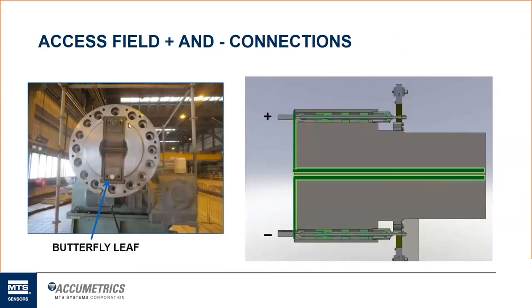So this is the end view of what the rotor has. And the exciter will have the exact same coupling, just like this. So those field voltage connections and the plus and minus are run through the bore of the rotor itself and the exciter rotor as well. And they're broken out into what's called this butterfly leaf assembly.